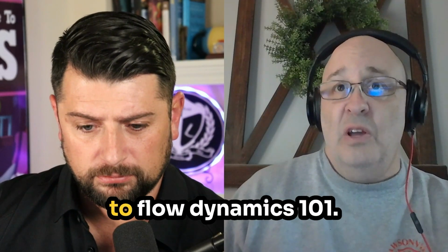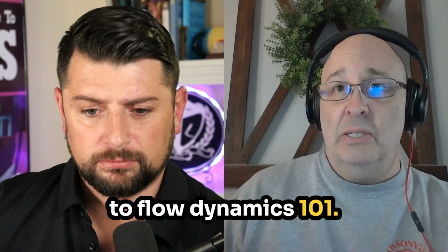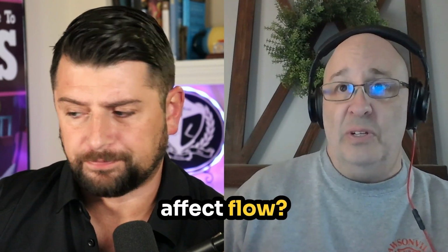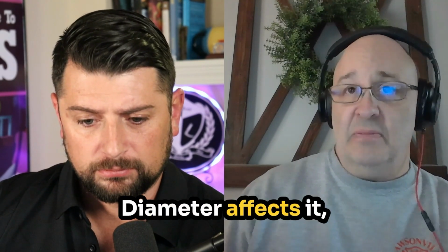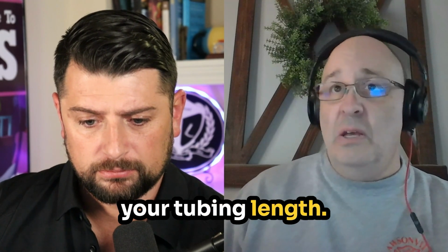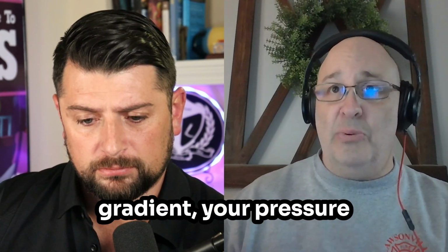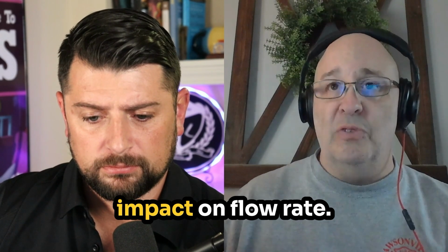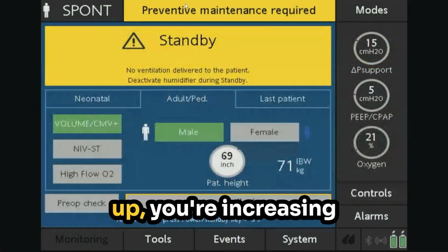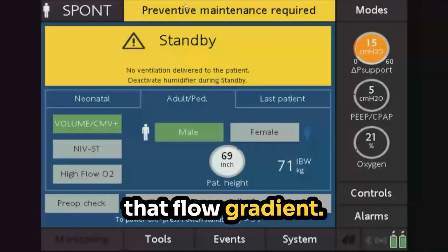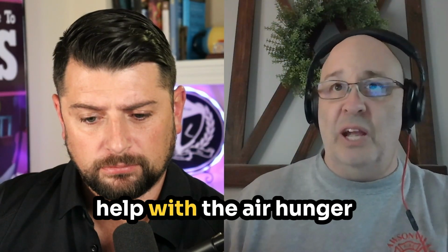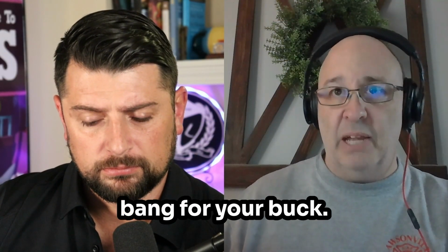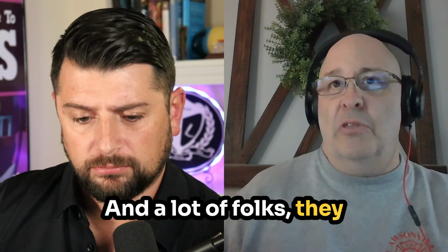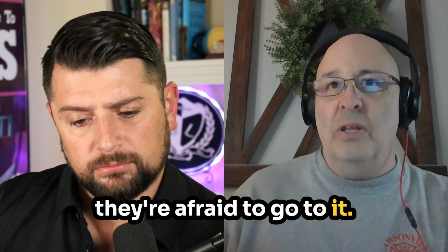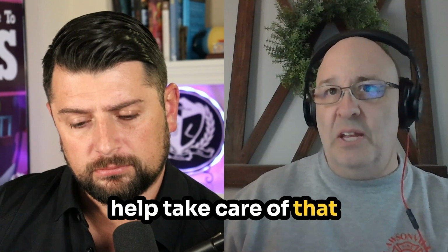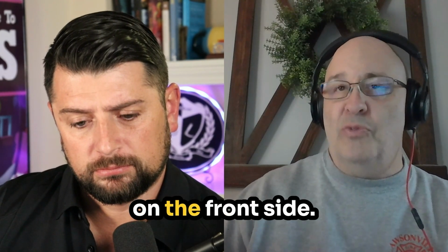It's really taking you back to flow dynamics 101. What 3 things affect flow? The diameter affects it, viscosity, and then your tubing length. But if you look at P1, P2 gradient, your pressure gradient has a huge impact on flow rate. And when you turn your pressure support up, you're increasing that flow gradient. That's what's going to help with the air hunger more than anything. That is the biggest bang for your buck. And a lot of folks, they don't think to go to it or they're afraid to go to it. But that's going to help take care of that dyspnea, especially for someone awake on the front side.